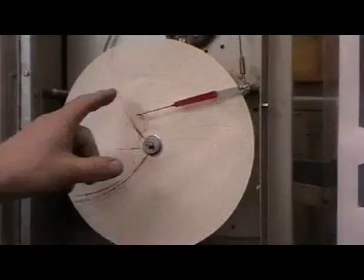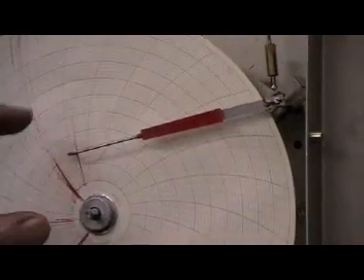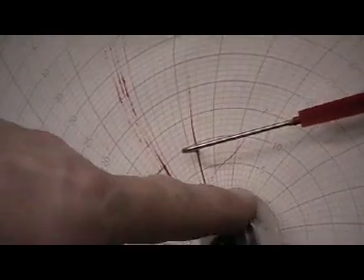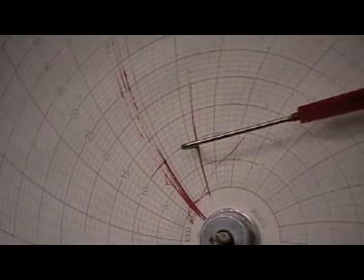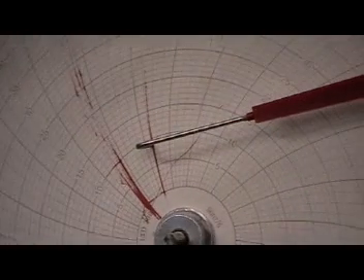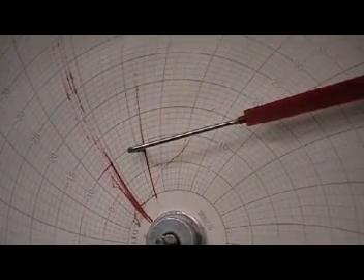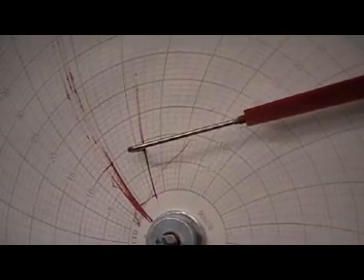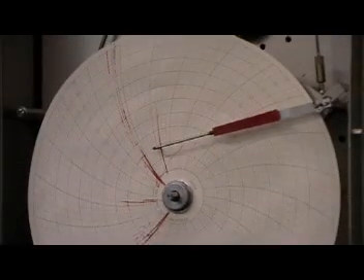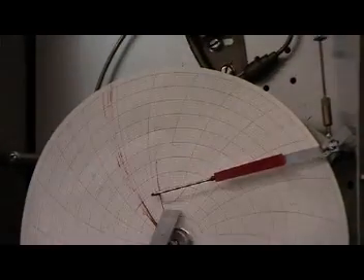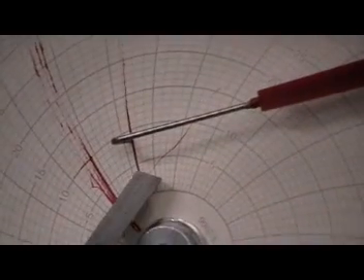As you can see at the moment it's measuring 900 psi. This is 0-5000. Each one of these divisions is 50 psi. We claim the normal calibration accuracy of our chart recorders is plus or minus 1%. 1% is one division on a 5000 range chart which equates to 50 psi.